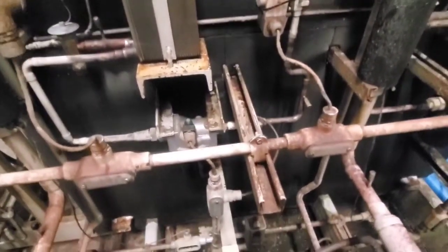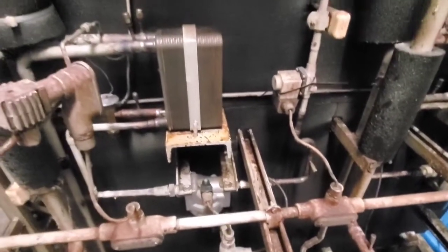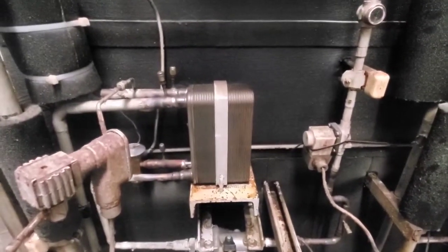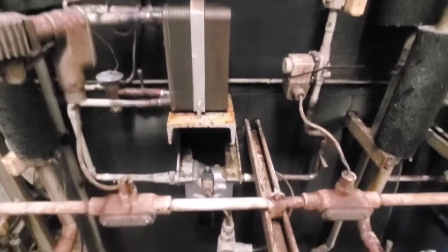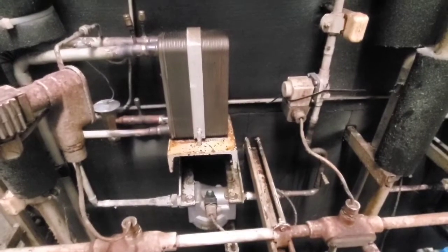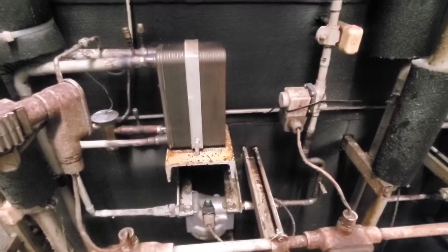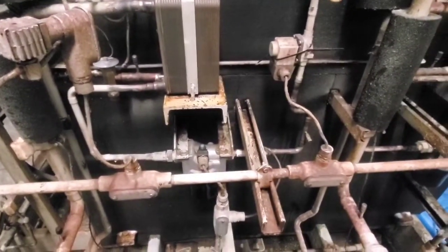Alright, so we got a vacuum pulled on the system. We got oil in it before we did that. One thing about this system, as I mentioned before, is that some of the isolation valves leak by. So we're not going to be able to pull a 500 micron vacuum. We just got to do the best we can. Now I've opened up all my isolation valves, and the unit is ready to crank up on this circuit now.